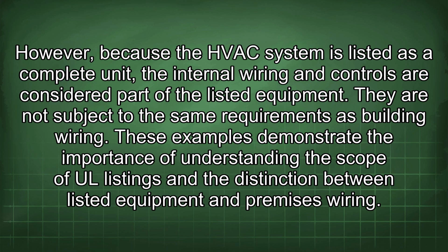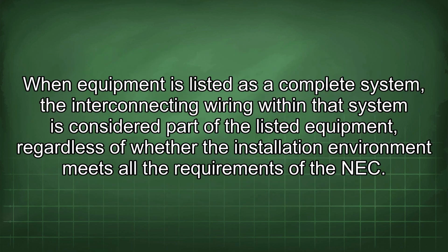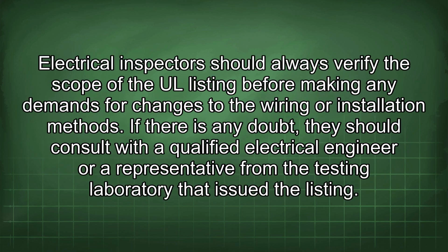These examples demonstrate the importance of understanding the scope of UL listings and the distinction between listed equipment and premises wiring. Where equipment is listed as a complete system, the interconnecting wiring within that system is considered part of the listed equipment regardless of whether the installation environment meets all the requirements of the NEC. Electrical inspectors should always verify the scope of the UL listing before making any demands for changes to the wiring or installation methods. If there is any doubt, they should consult with a qualified electrical engineer or a representative from the testing laboratory that issued the listing.